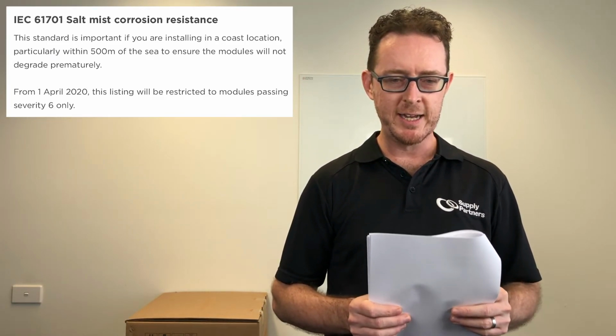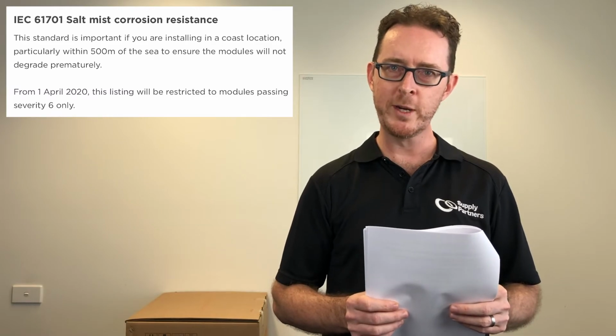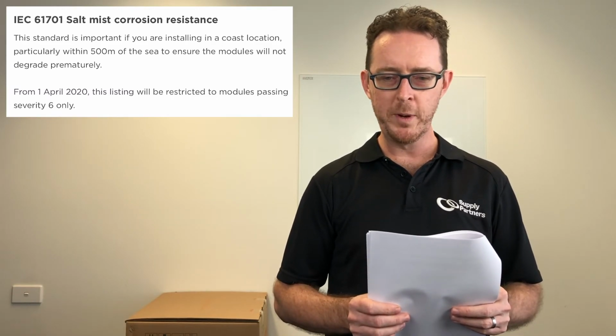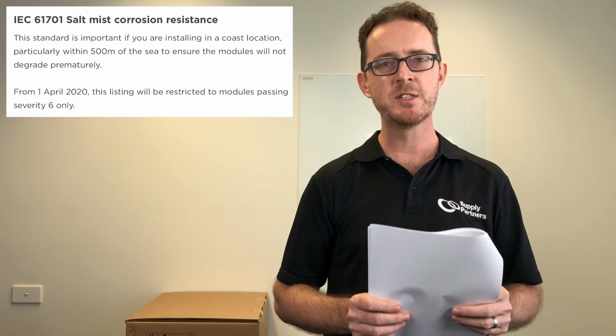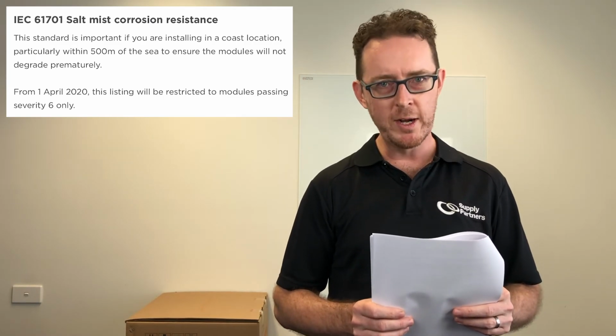But they are saying now from 1st of April 2020, this listing will be restricted to modules passing severity level 6 only. So despite the fact that they're saying in coastal environments within 500 meters of the sea, and the fact that that refers to level 1 of the international standard itself, they're saying from the 1st of April 2020, only modules with severity level 6 will be considered to have an enhanced listing. I want to know why.